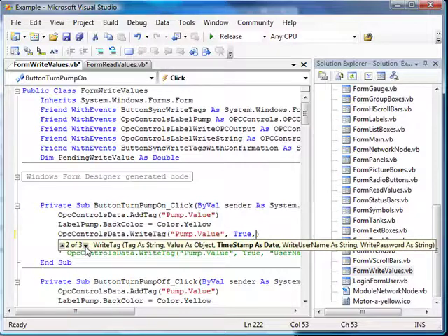This way your Visual Studio application becomes the data source for this OPC Systems.net tag. If the tag data source itself is set to value, then it will use the timestamp that you write from your application, which will then be populated out to all the features for alarming, trending, data logging, OPC client interface, and also OPC route to write the values back to an OPC server.